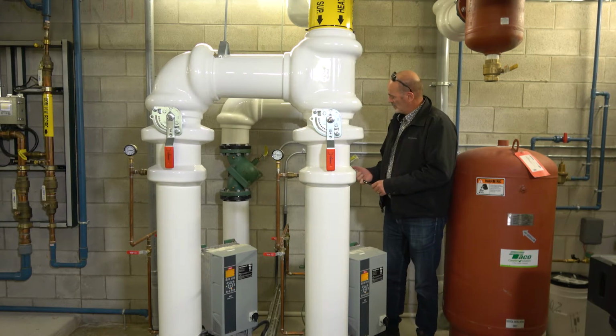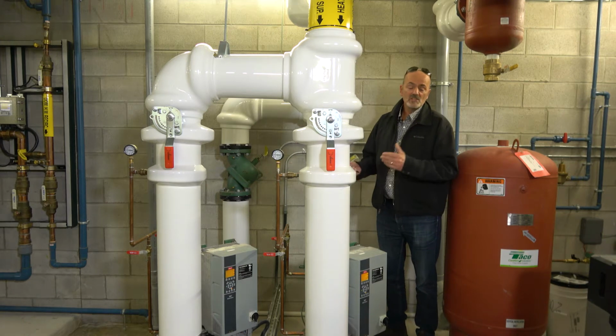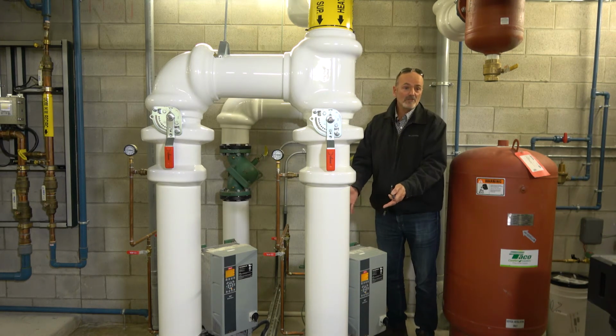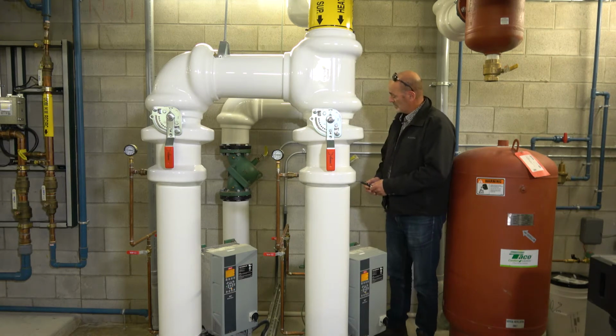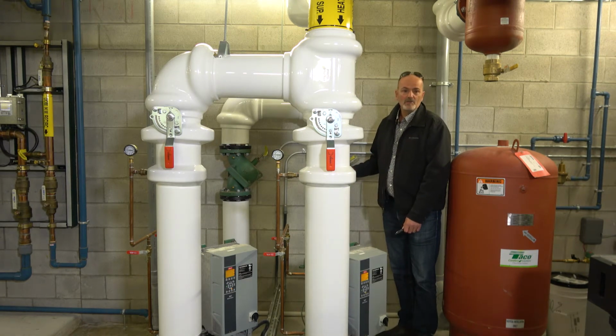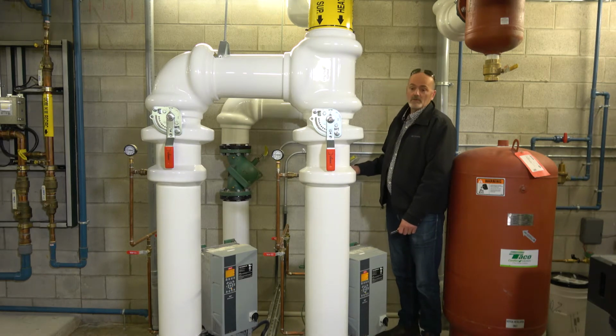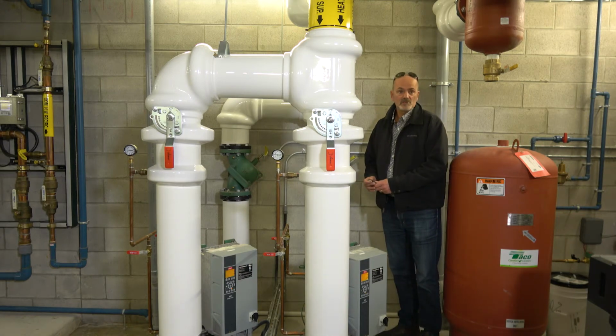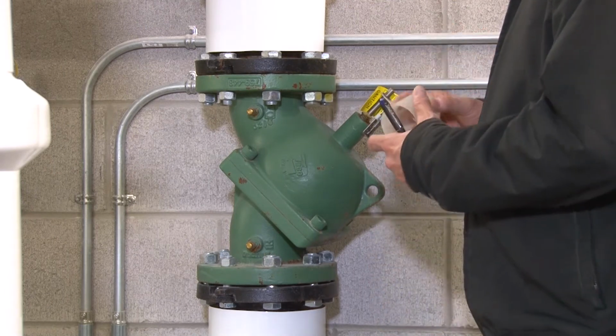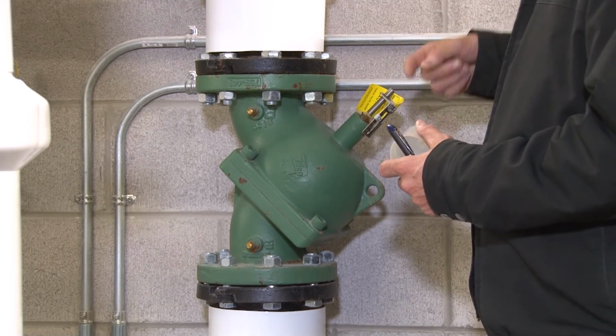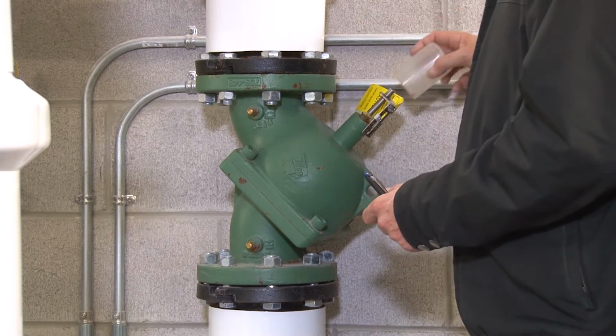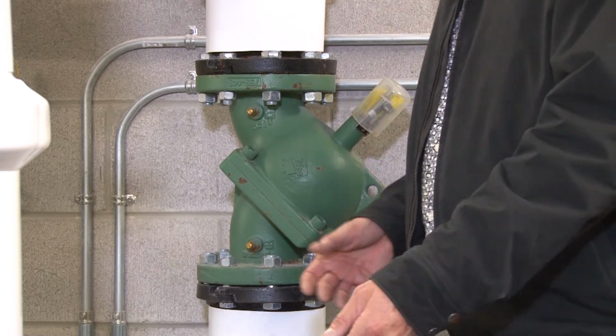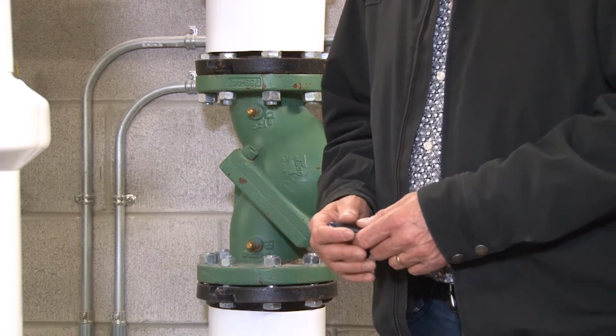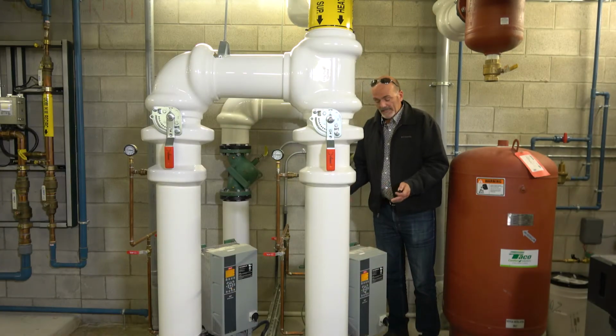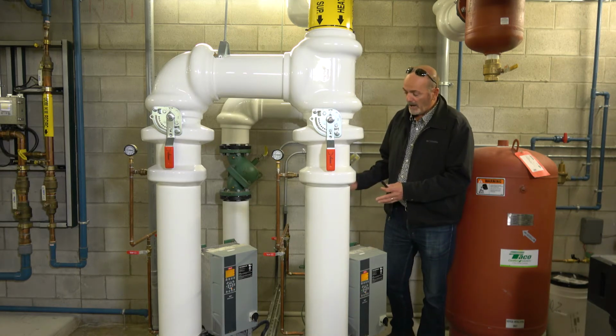So one is check. Two is it's also a balancing valve, but that's kind of redundant here because we have self-balancing pumps based on pressure response in the system. So in this case, the balancing valve is probably not even used. It's probably fully open. Okay. So the third function of the valve is its positive shutoff. So this particular bolt here, you spin it, closes the valve, locks it down for when you want to do any isolation purposes for maintenance of seal replacement, cleaning of the strainer, and so forth. Okay. And that's basically the operation of the pumps.